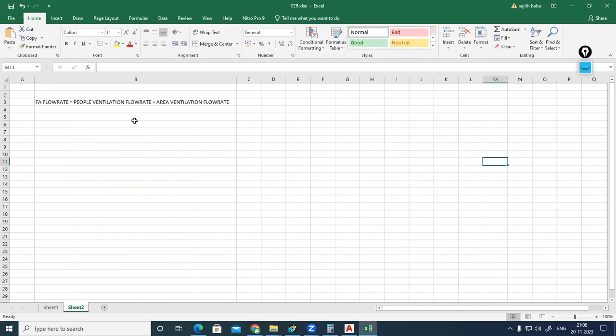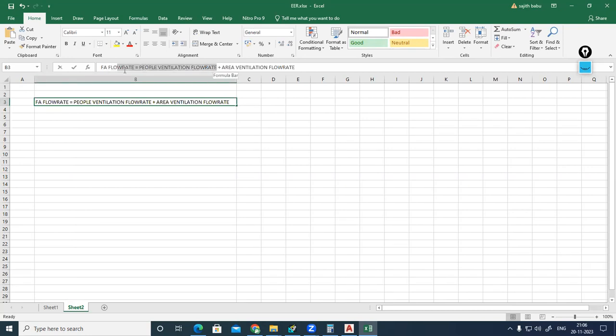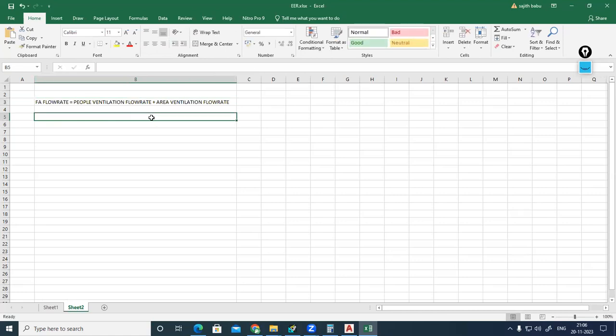Anyhow, the first one, people ventilation flow rate, we can calculate, right? People ventilation flow rate in liter per second only, normally we will be calculating it. People ventilation flow rate in liter per second is equal to the number of people within the space multiplied by the RP value. This RP value we should take from the ASHRAE 62.1 ventilation standard. For the training room, we are dealing with the training room only.